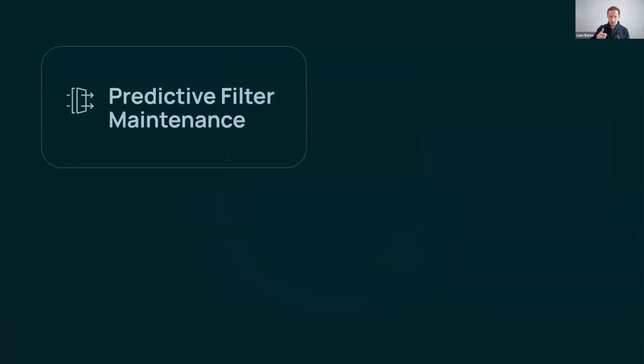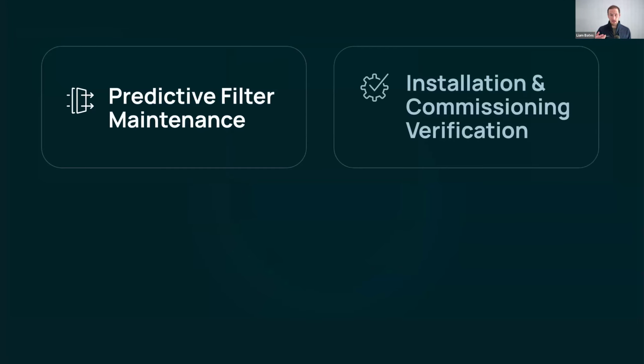This unlocks predictive filter maintenance using data, not fixed schedules. It makes installation and commissioning verification actually possible. There were some great posts on LinkedIn I saw a while ago about diagnosing a building with high PM 2.5 levels. The team was happy they traced it back to a filter that hadn't been installed properly — air was going around the edge instead of through it. It's great that air quality monitoring within the space unlocked the ability to work out that root cause, but that was after it impacted people, working backwards to find the problem. With this data, you would see the problem immediately.